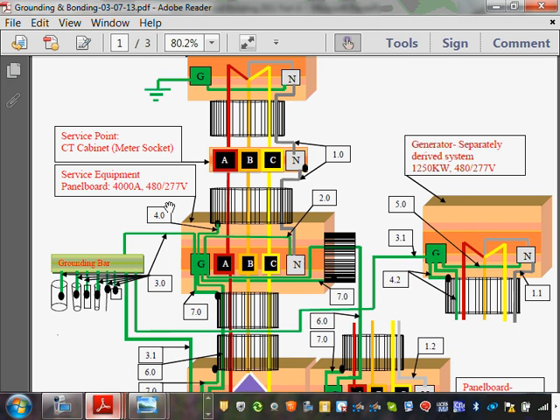Any comments, any questions about number 2, guys? So I have my own grounding electrode system for all my enclosures. The utility has grounded their system, and I want to tie their ground to my ground. I tie it through the neutral up to here, but inside the switchgear, I have to tie my neutral to the ground that I own and operate and created. That conductor here is called 2.0. It's called the main bonding jumper. Any comment about the main bonding jumper? How do you size that main bonding jumper? Why do we do that first? Why do we do that? That's how you tie into theirs.